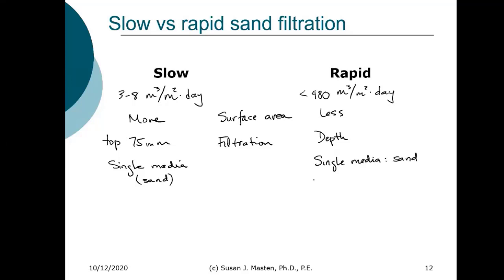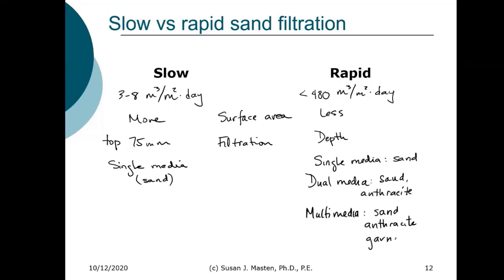We can have dual media, which is typically sand and anthracite. And we can have multimedia, which typically is sand, anthracite, and garnet. And we use these different media because they have different specific gravities, they have different sizes and porosities, so we can use them to remove different particles.